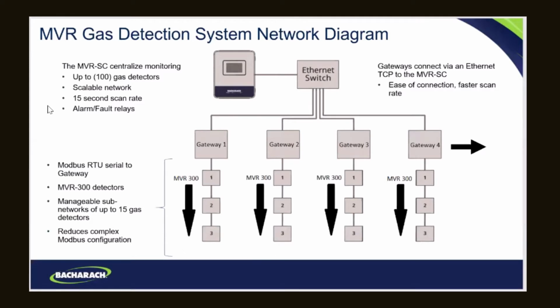But this is essentially what the network looks like. So you've got the controller. You're going through an Ethernet switch. That Ethernet switch can be 4-port, 8-port, however you scale it, but there is a limit to the controller of 100 connected gas detectors.